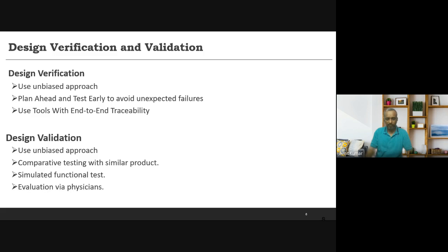Use tools with end-to-end traceability. This requirement comes primarily from regulation. So for a simple example, if I have a component and I want to do a design verification on it, and the verification I am performing is on the length of the product, I could use anything from a very simple scale to a vernier to a visual measurement system. The question is, is it reliable or is it satisfactory? Is the device we are using trustable? That is what we mean by traceability. Today, when we are working on design requirements, the entire design team is available, the entire testing team is available. But tomorrow, some of us may not be available. So how do we ensure that tomorrow, when there is a design change and somebody is doing it, we have done it correctly in the first place? This end-to-end traceability ensures that things happen properly, correctly, and in control every time.